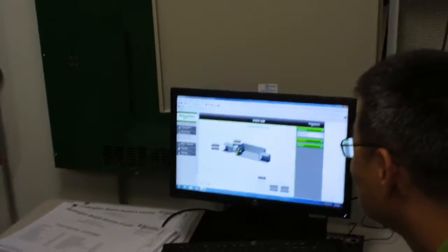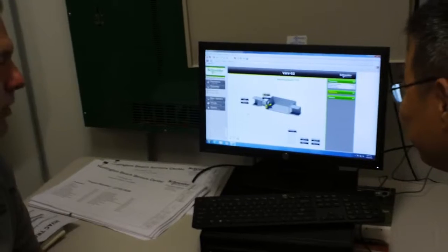One of the last ones we did with Climatech, what they did is they had the damper position linked to the command. So when that said 99%, that damper could be slammed shut, stuck with a screw. But because they were going off of their command rather than a feedback, it was useless. This is way better. It could be one where the screw got loose from the shaft and it's opening, but it's really not open.